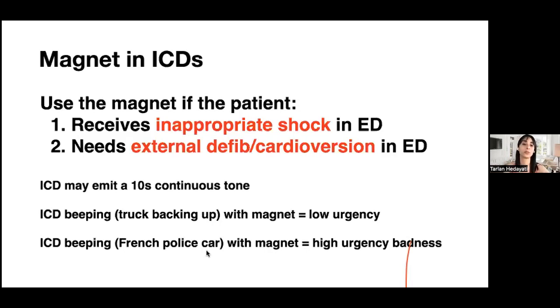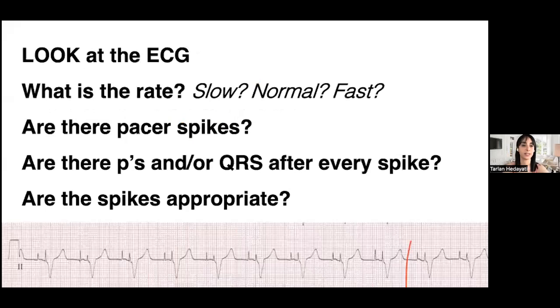If you get that French police car alarm sound, that's a high urgency alarm. There's something wrong with the ICD, and so we will then call the electrophysiologist to come in and do an interrogation and figure out what's going on with the device. So, two scenarios only where we use a magnet on an ICD.